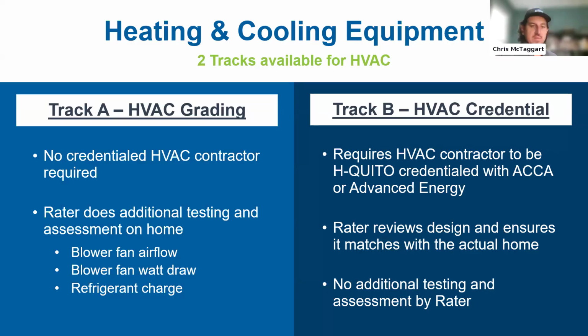The types of testing and verification we're talking about are testing the total system airflow on the HVAC system. So the air handler itself, when you do a design for HVAC systems, typically air handlers can run at several different speeds, and their airflow can potentially be sensitive to things like restrictions or duct sizing. Testing the airflow to make sure that we're actually getting the proper amount of airflow as per the design is something that the rater might do as part of that HVAC grading process. Concomitant with that would be testing the blower fan watt draw. Again, certain blower fans are sensitive to back pressure, and they may increase their electrical consumption if met with significant resistance. And so the rater is able to test the watt draw of air handler systems.